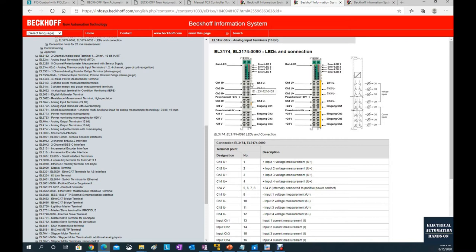For the voltage channel wiring, it is quite straightforward — channel 1 and channel 2 each have a plus and a minus terminal. However, for the current channel, look at this area — it is special. There is 24V here, and the actual current inputs are on the right side. You'll notice there are no negative terminals for the current. This brings up the topic of two-wire versus four-wire sensor wiring, which depends on whether you are using two-wire or four-wire sensors.